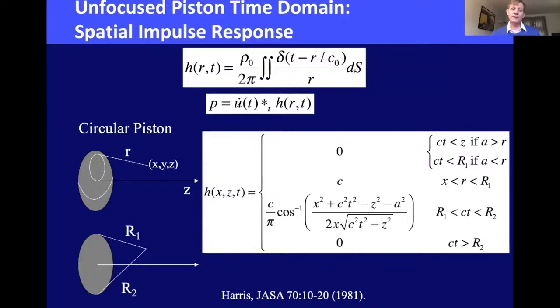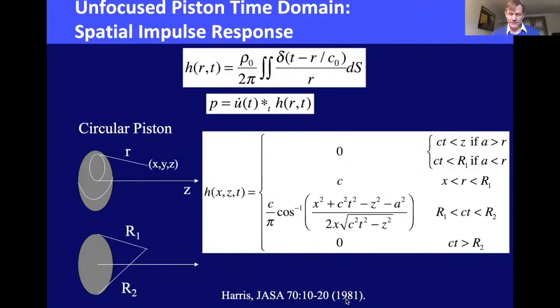Going off-axis, the solution must be split into cases depending on whether integration circles are complete or not. The pressure can be written as a convolution between particle velocity and the spatial impulse response — the field produced by a delta-function source. A paper by Harris from the 1980s provides the analytical expression for this impulse response for a circular transducer.